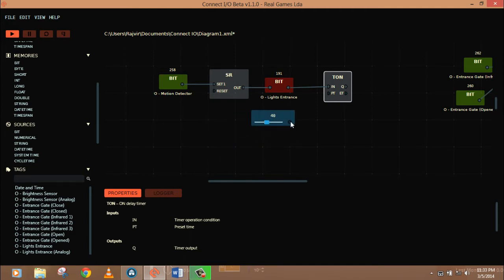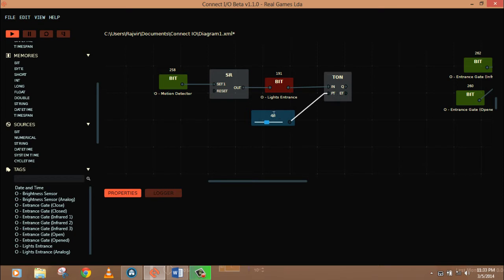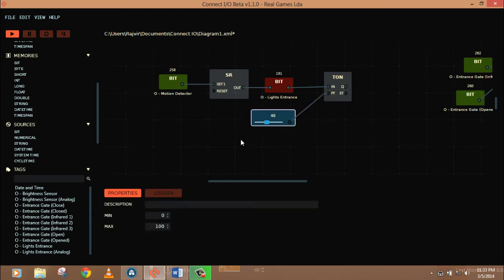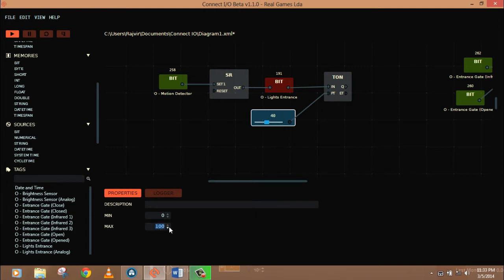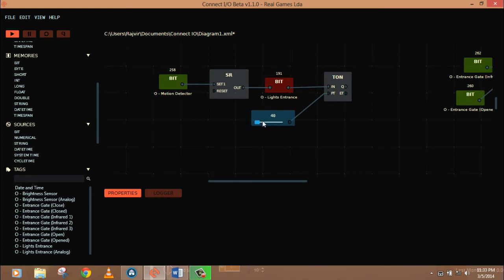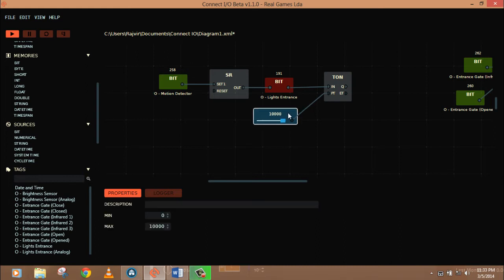This is the process time. So now this is the time which we want a delay. We want to delay for this particular time. So for that, what we're going to do is we're going to increase its maximum value, because in this timer if we take 1000, it means one second. Time basis is milliseconds. So we have to increase that to at least 10,000. Now it has maximum value of 10,000, which is 10 seconds. So let's have 10 seconds time. Now what will happen after 10 seconds? We are going to actuate the reset here, but you cannot do that directly. This cannot be done directly.